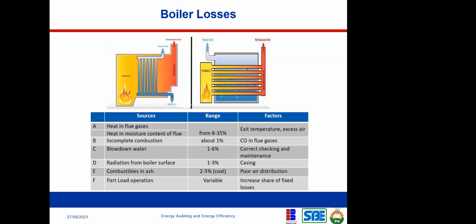Okay. And how do you know when you have an incomplete combustion? When there is carbon monoxide in your flue gas, it tells you there's an incomplete combustion. Carbon monoxide tells you there's an incomplete combustion. But if you're seeing carbon dioxide, then that means a complete combustion. So there's what we call boiler blowdown water.